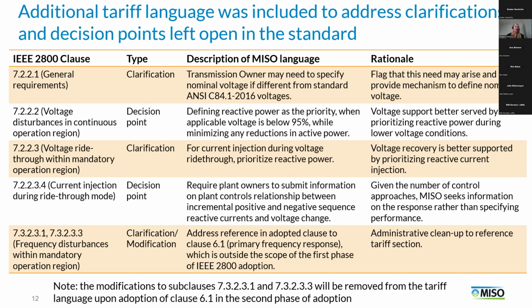And then the second decision point was for the subclause that covers current injection during ride-through mode. As Wes mentioned, the standard does not specify the magnitude of incremental, positive or negative sequence reactive current injection that is required during a fault. But what the standard does say is that the TS owner should consider specifying that based on system needs. So what we did is in our tariff language require the interconnection customer just to submit information on the plant's default relationship between incremental reactive current and voltage change. And then the language states that MISO or the transmission owner can specify a required relationship that's different than that default if necessary. Okay, and that covers all the extra tariff language. So we really tried not to modify any 2800 language except for that specific case where we altered the reference to clause 6.1.